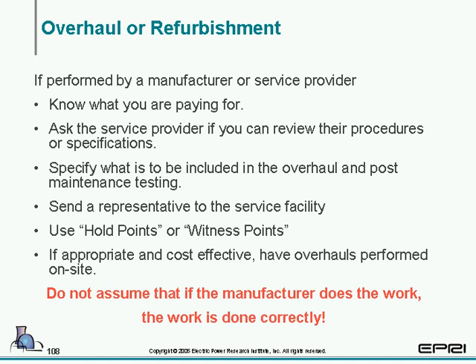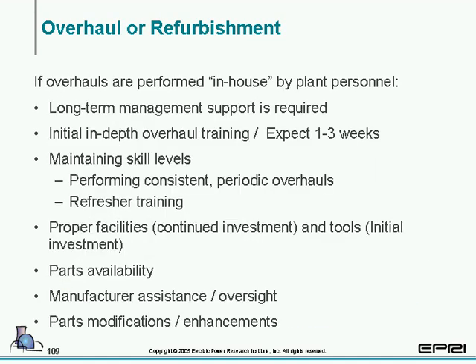And the main thing I do want to stress is, if you're sending your breaker out to the manufacturer, and you say, well, they're the ones that manufactured the breaker, and they're the experts on it, don't assume that the work is going to be done correctly. In other words, just because you send it to the OEM, that doesn't mean it's going to work correctly. Anyone that's working on a breaker, be it third party, your own plant technicians, or a manufacturer, you should check the work and perform some type of post-maintenance testing or checking.